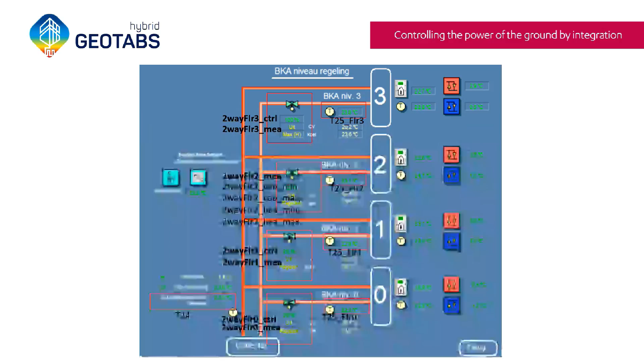Now to give you an idea of what we're actually controlling, we have some figures. This is an overview of the Priva interface, where we have these 4 two-way valves of the building. So those are valves that we are controlling. This is an overview of one of the floors, where you have the same two-way valve indicated here, but you also have some dampers for which we control the ventilation flow rate. So there's a damper for each of these 4 different rooms. And if there is a heating coil, for instance, as indicated here, then we can also control the flow rate going to that heating coil.